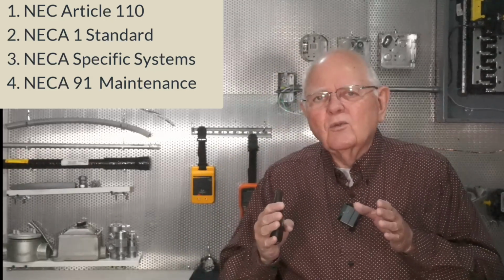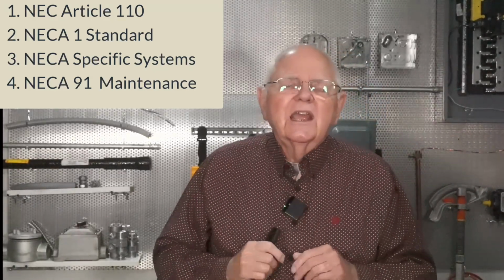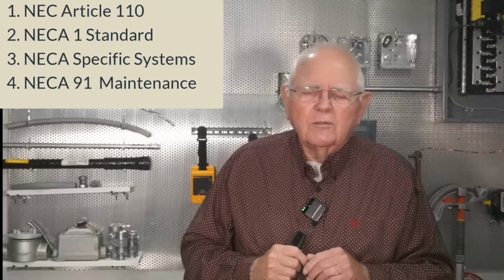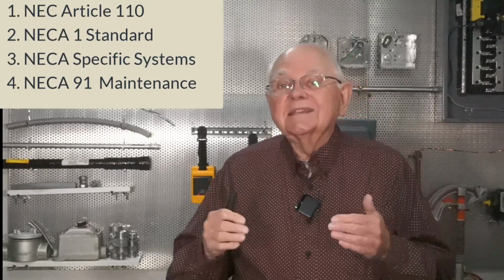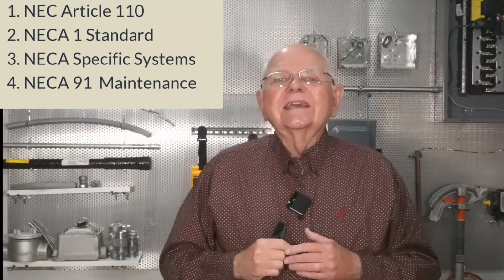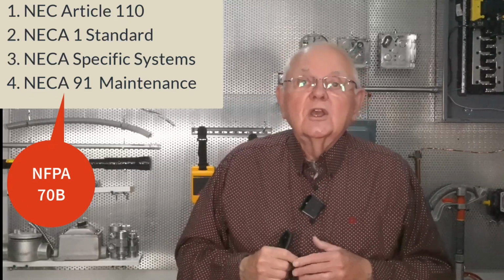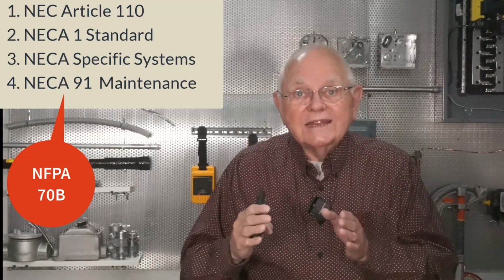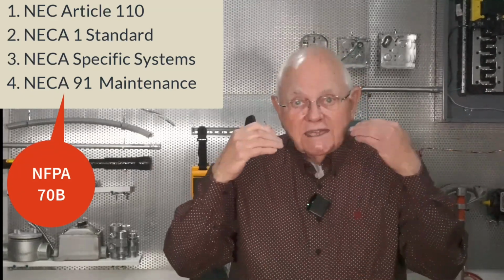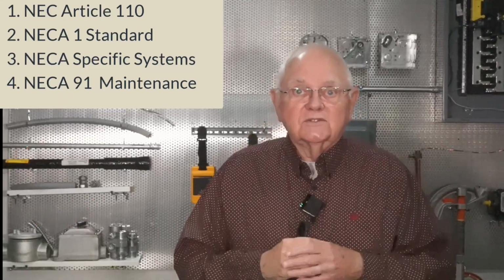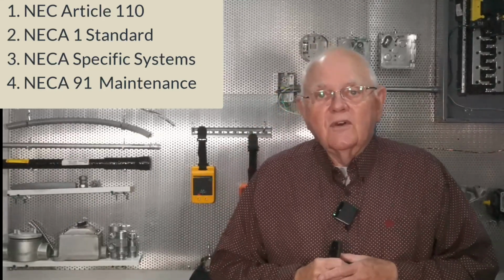We can look and see what the NEC has to say about maintenance of our electrical equipment, but of course the NEC is not a maintenance document. However, there's the NFPA 70B standard, which moved from a recommended practice to a standard. It's NFPA 70B, the standard for electrical equipment maintenance, so we do have to follow that one.